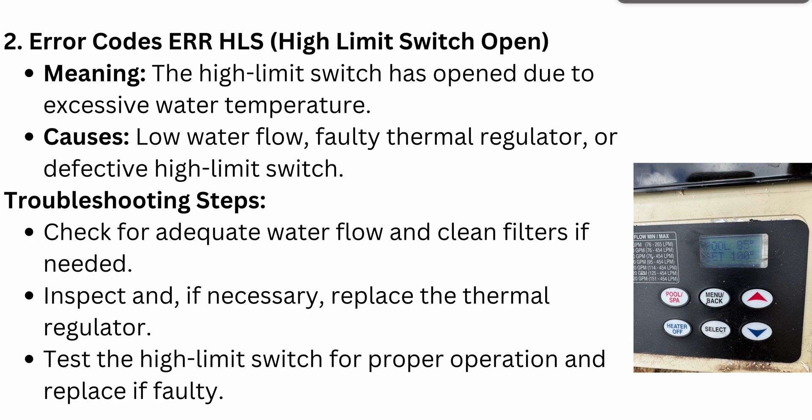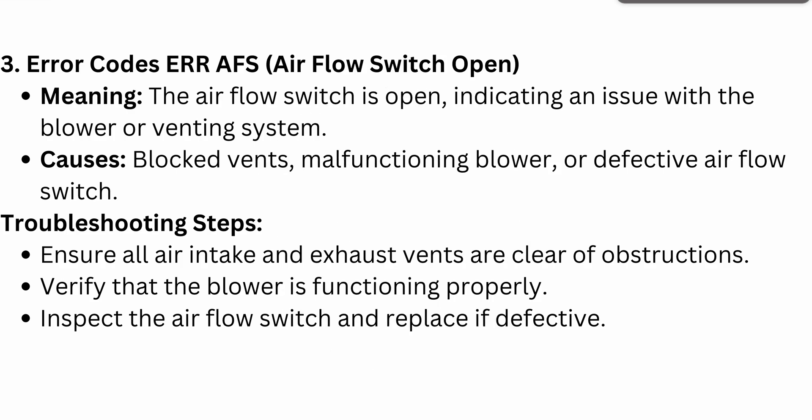To troubleshoot ERR HLS, check for adequate water flow and clean filters if needed — regular filter cleaning is one of the most important maintenance steps you can take. Inspect and if necessary replace the thermal regulator. Then test the high limit switch for proper operation and replace if it is faulty.